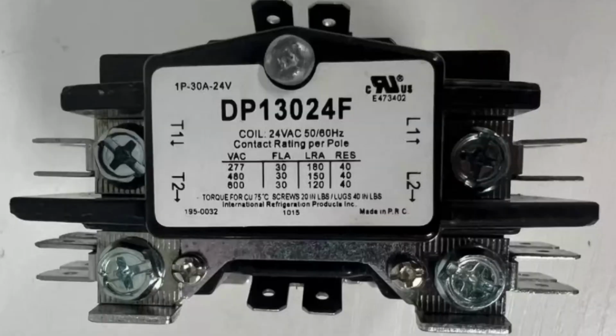Another misconception is it's going to be easier on your system overall. Now, a lot of us that are service techs and installers know that that's not true, because you do have a system that's going to come on and off more often. In fact, a lot of things, particularly the contactor, are worked out more heavily. So you may have premature failure in a number of parts because they're really not built to withstand the rigors of zoning. Contactors is the example I use the most because you have a unit that's starting and stopping a lot more often.